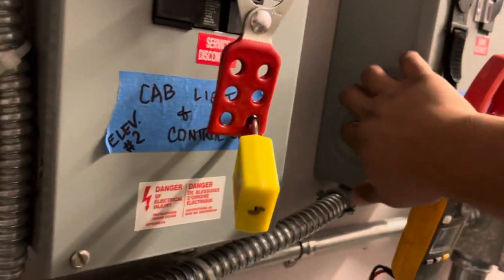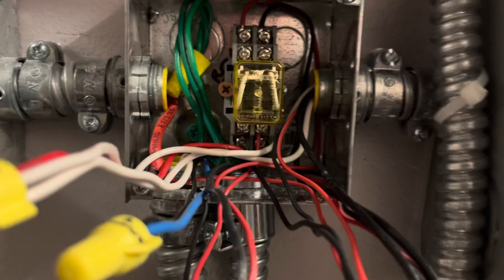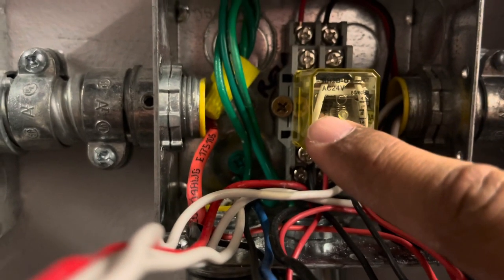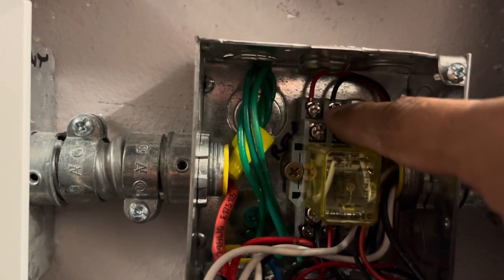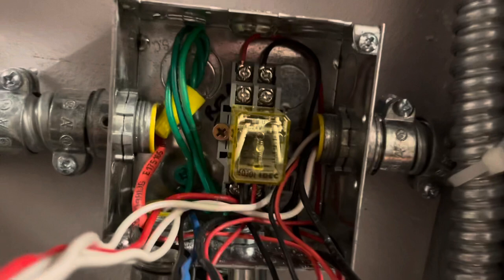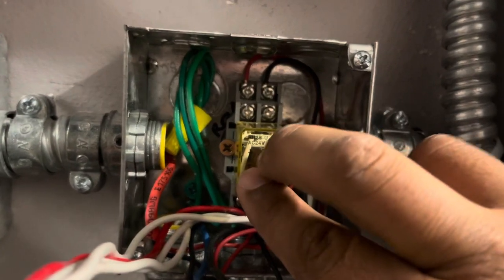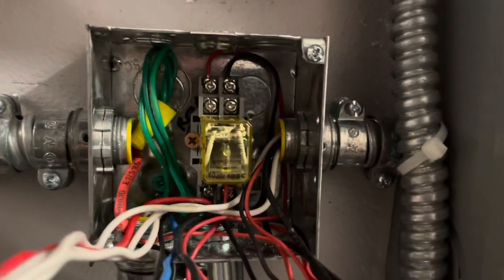Your load of the 120 will go to the shunt right here and then the shunt up here. So that's where the load goes, and the load goes on the normally closed position, which in this particular case is 5 and 8. So 5 and 8 are up here, and that's why they go up there, because you do not want them to be on. So when this thing closes, it will automatically sense, close it, and then bring 120 to this.